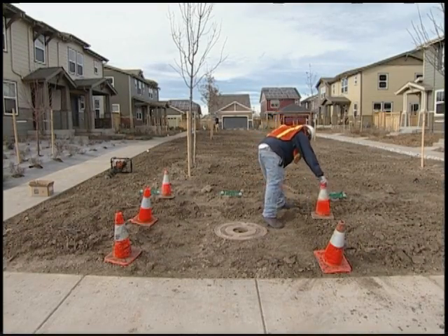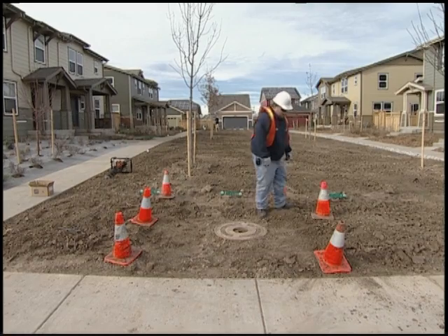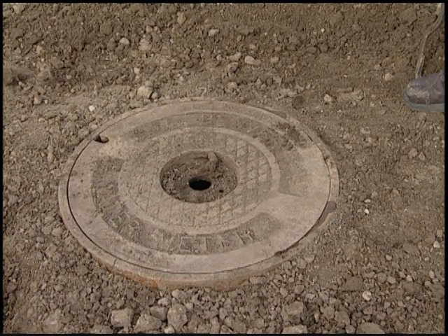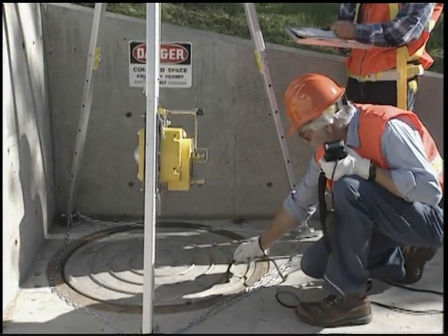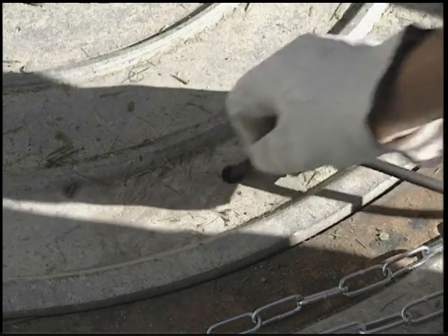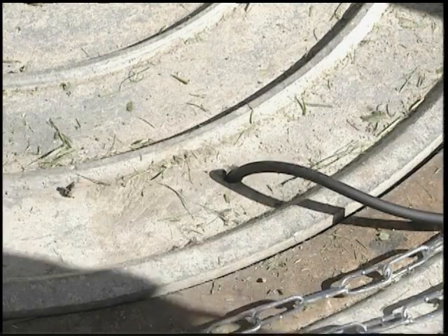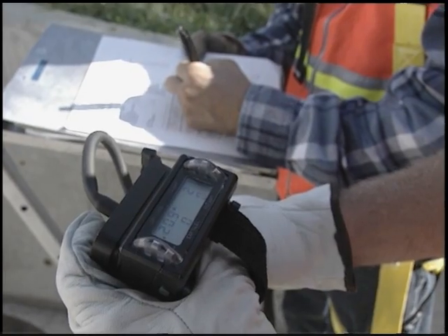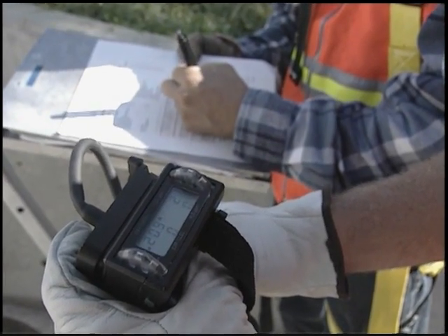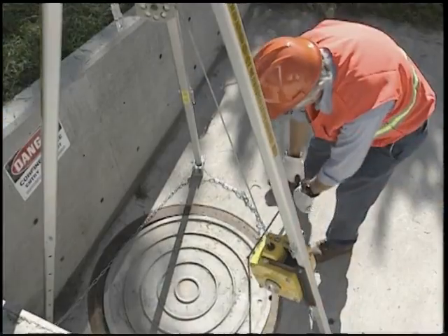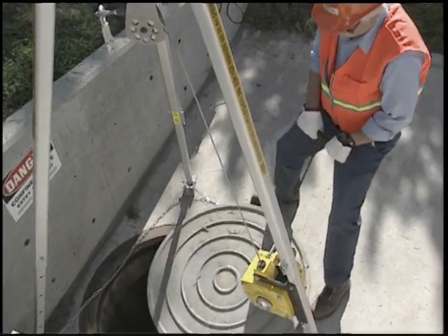If possible, test the confined space atmosphere without removing its cover, as in the case of a manhole or entry cover that has a hole for a sampling hose to be inserted. Insert the sample hose approximately 6 inches through the hole to conduct the first test. Oxygen 20.9, CO, explosive 0. If no combustible gas is found, then the cover can be removed or door opened for further evaluation.